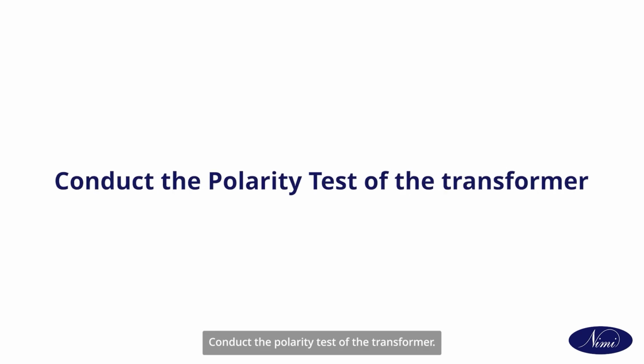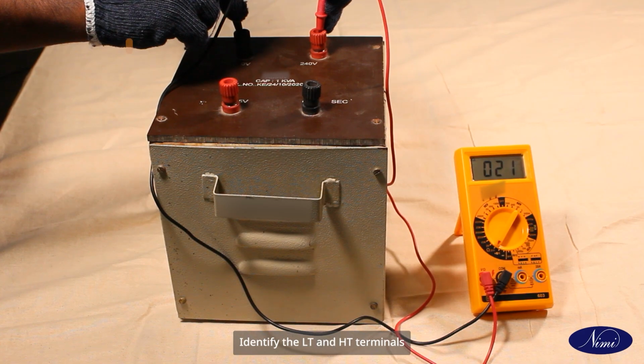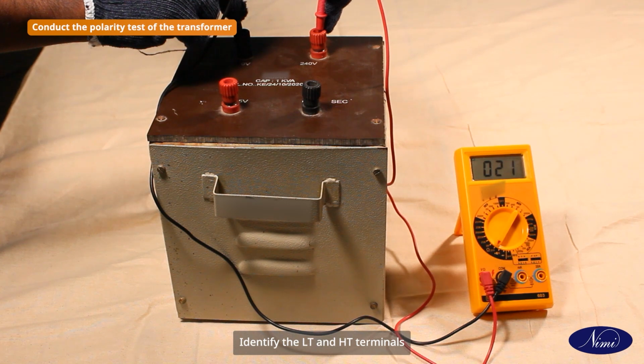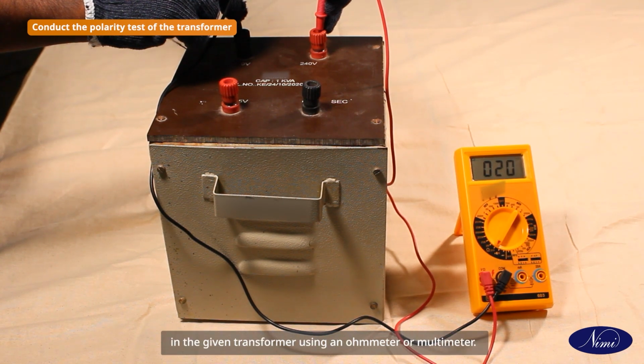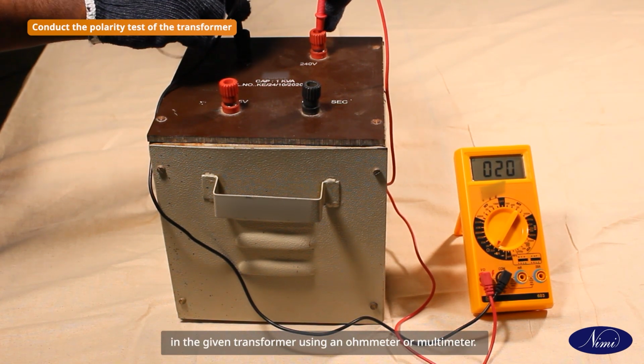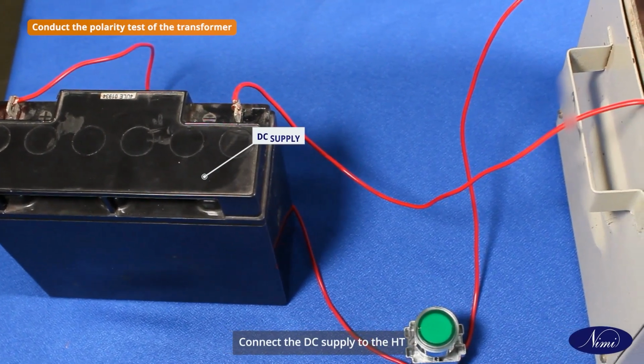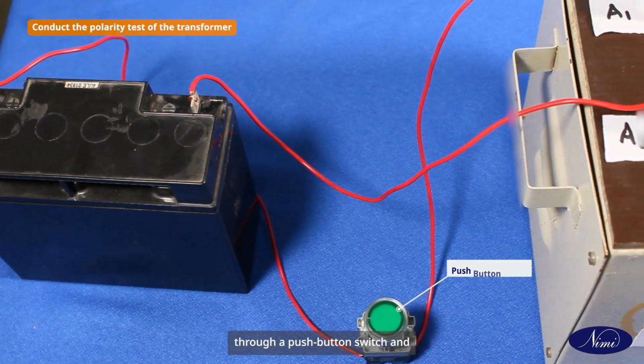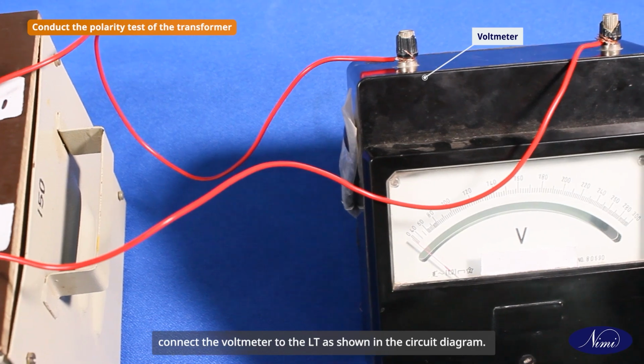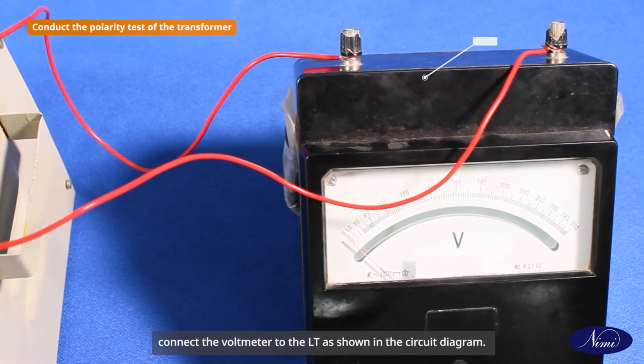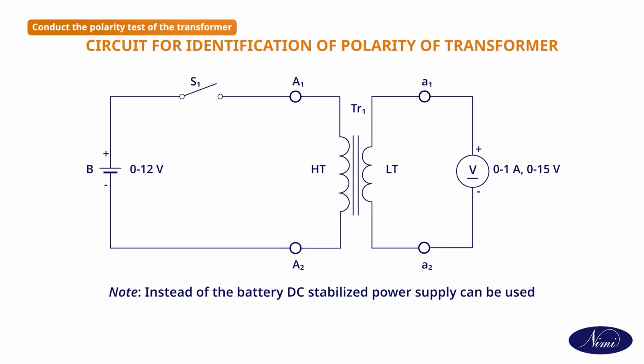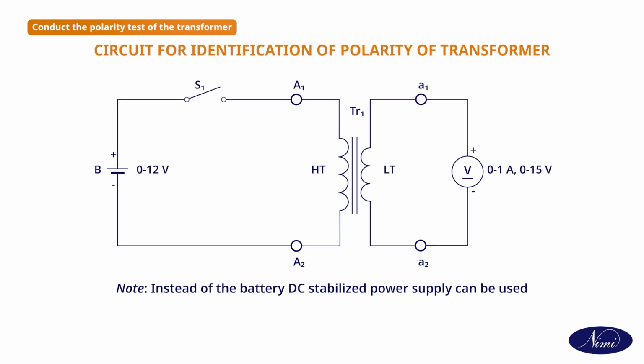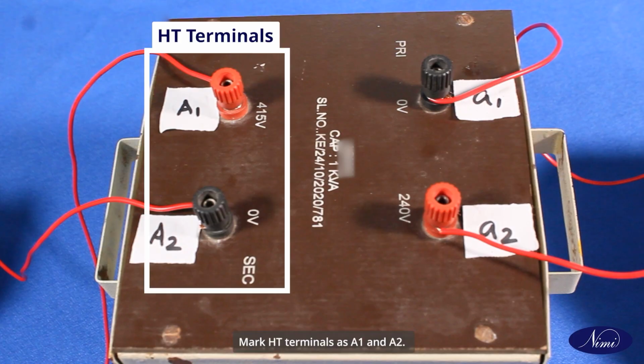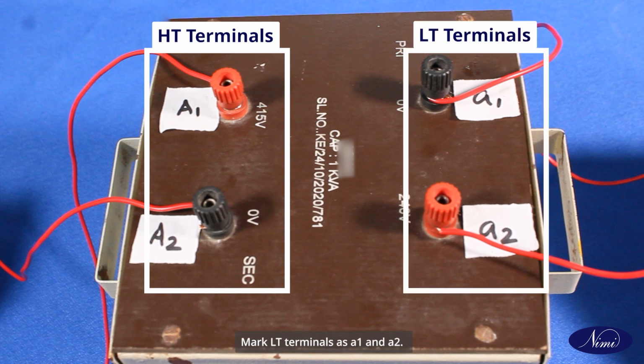Conduct the polarity test of the transformer. Identify the LT and HT terminals in the given transformer using an ohm meter or multimeter. Connect the DC supply to the HT through a push button switch and connect the voltmeter to the LT as shown in the circuit diagram. Mark HT terminals as A1 and A2. Mark LT terminals as a1 and a2.